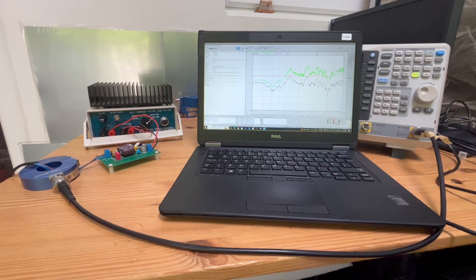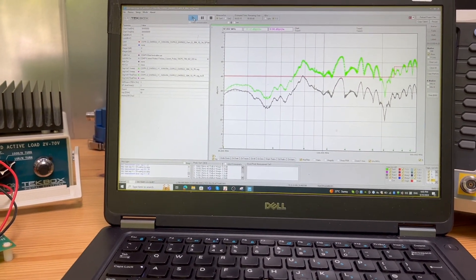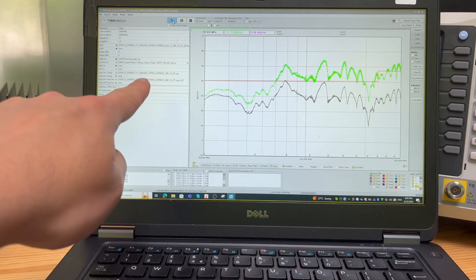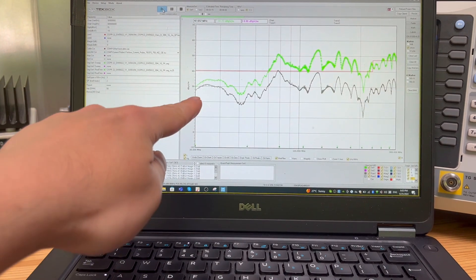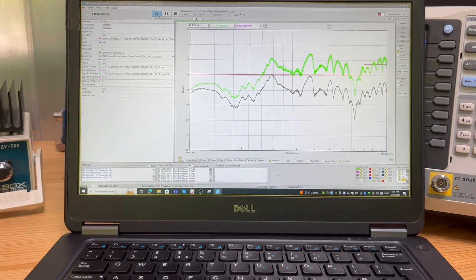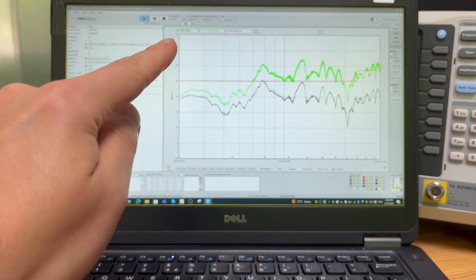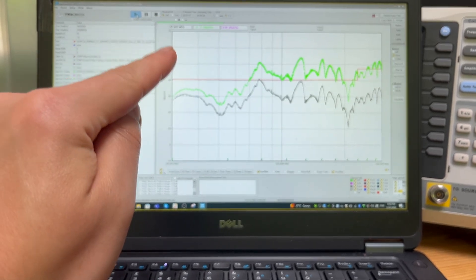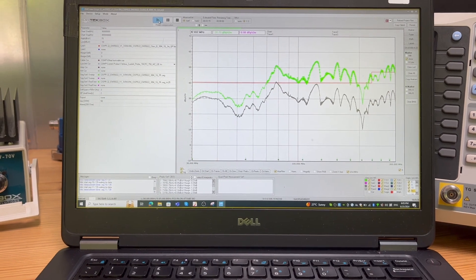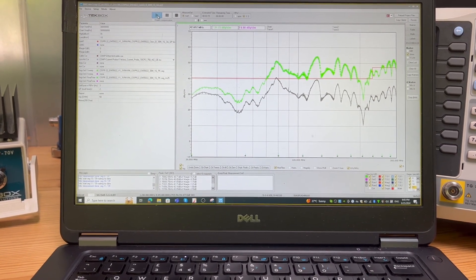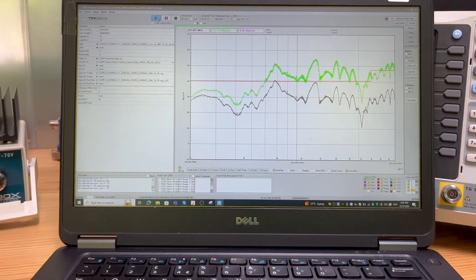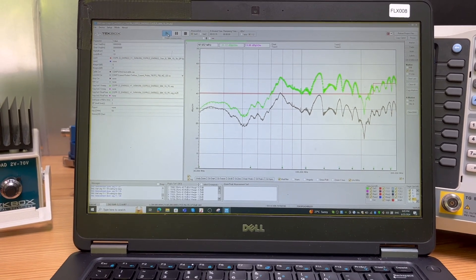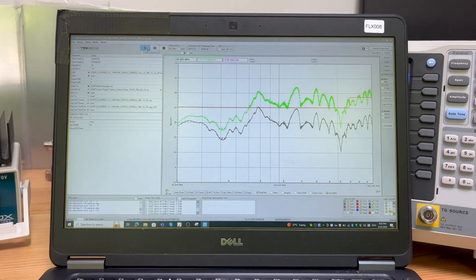In order to answer that question, let's have a look at this result. You can see here, this is the algorithm we use to predict the far field. As you can see, there are two curves, one is showing in green and one is showing in gray. The green is the predicted far field results against the limit line showing there. The limit line currently is Class B limits, and the gray line is actually the raw data. That's really the data in terms of you measure it, and then that's how the spectrum analyzer reading looks like. The gray curve is the raw data read by the spectrum analyzer, so that must be in dB microvolts then.